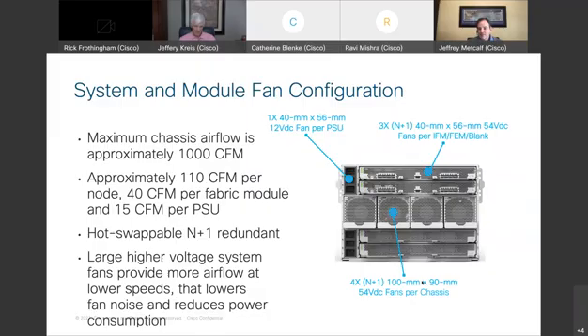We basically have 4 system fans. These are 100 millimeter fans. The reason for selecting 100 millimeter fans above the 80 millimeter fans that you see in the current 5108 is that these larger fans let us operate at lower fan speeds and move the same or more air volume. But by operating at lower fan speeds, we can reduce power.